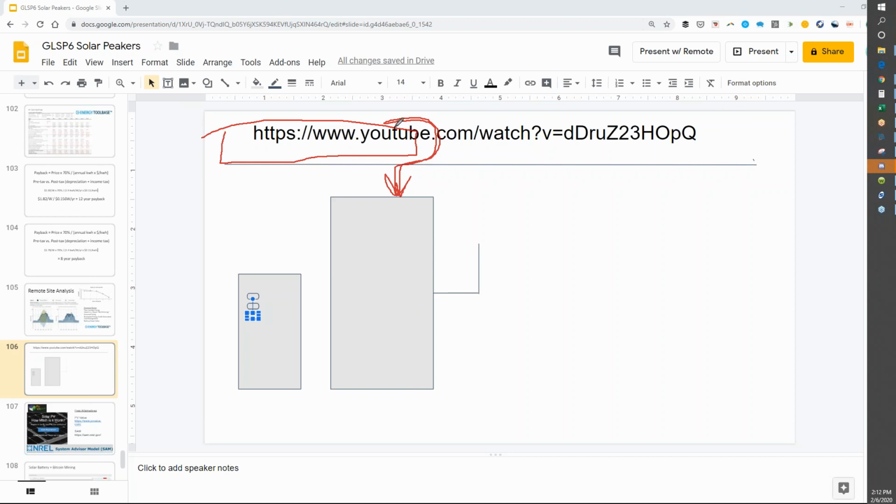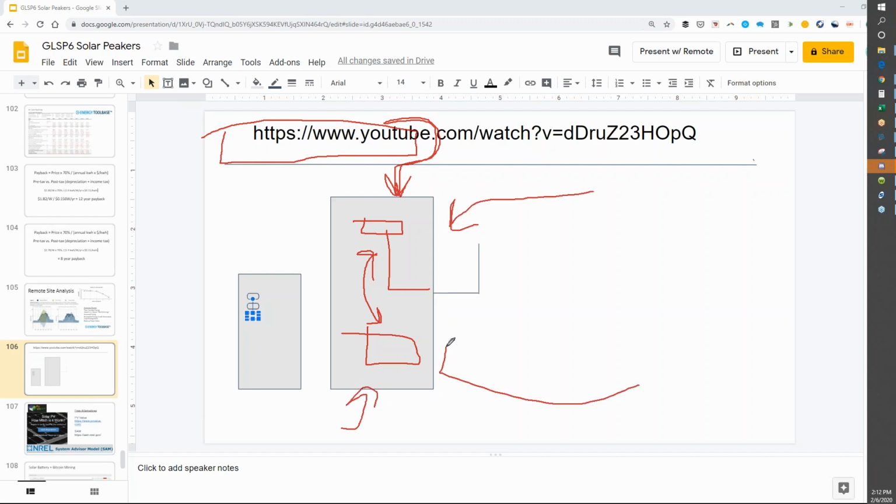And so the mistake is, you've got two terminal blocks at the top and the bottom of this disconnect switch, and the disconnect switch moves a blade between the two. And so the question is, where do you land the solar side and where do you land the utility side? Which goes on the top and which goes on the bottom?